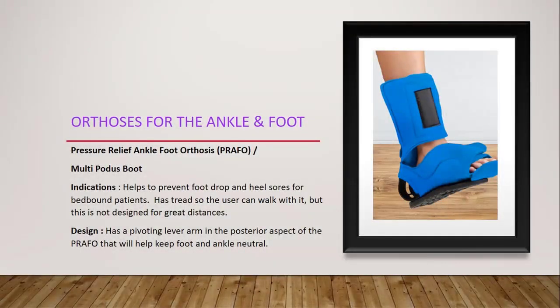Pressure relief ankle foot orthosis. The acronym is PRAFO. Many people also refer to it as a multi-podus boot. The indications for this type of orthosis are: it helps to prevent foot drop and heel sores for bedbound patients. It has treads so the user can walk with it, but this is not designed for great distances. The design has a pivoting lever in the posterior aspect of the PRAFO that will help keep the foot and ankle at neutral.